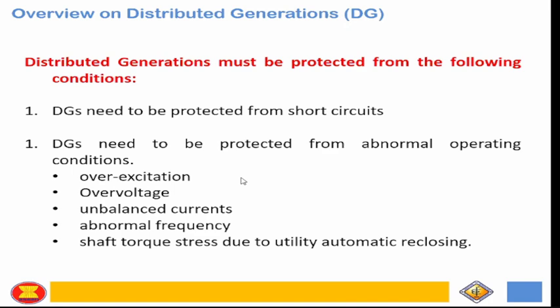So in that case, if hindi mo ma-maximize yung capacity ng generator because of that excessive unbalance, there's a negative sequence capability curve din yung generator. Then although you can operate, but not exceeding the limit of the negative sequence capability of the generator. Okay, that's for the unbalanced current.